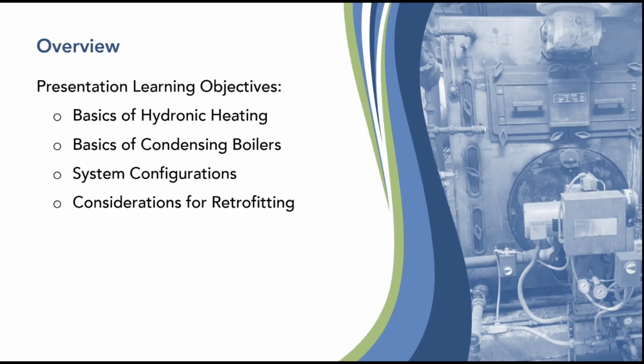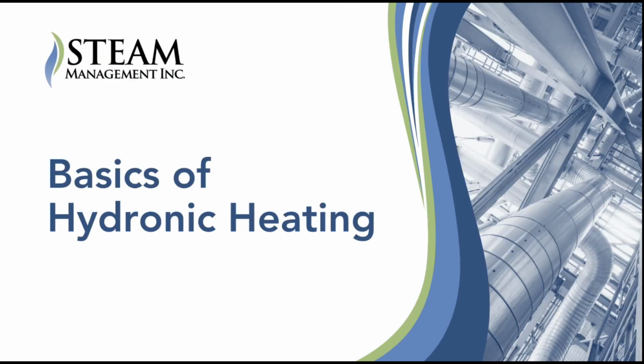Okay, so today's overview, we're going to talk about the basics of hydronic heating, the basics of condensing boilers, some system configurations, and your considerations for retrofitting if you're considering condensing boilers. So, basics of hydronic heating. For hydronic heating, we're talking about a hot water heating system or a glycol and hot water mixture in the heating system, not steam. Condensing boilers are for hydronic heating systems only, not steam replacements. If anybody mentions condensing boiler in the context of steam, they're talking about maybe a condensing economizer or something like that. And we'll talk about why that is later.